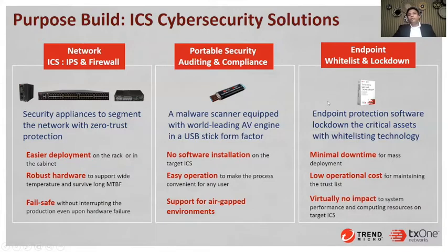So moving forward, new EXEs, new ransomware attacks, and malware attacks cannot execute, even if they have administrative rights. And that approach really helps because it doesn't take much of your system's resources, and because it's whitelisting, I don't have to update regularly. It also helps to do a configuration lockdown. For example, if I want to lock down PLC configurations or even HMI configuration files, we can lock those down as well. There are multiple approaches.